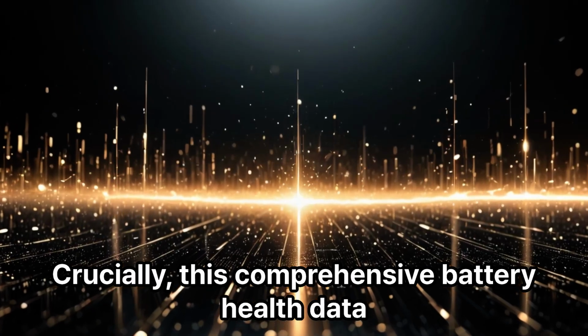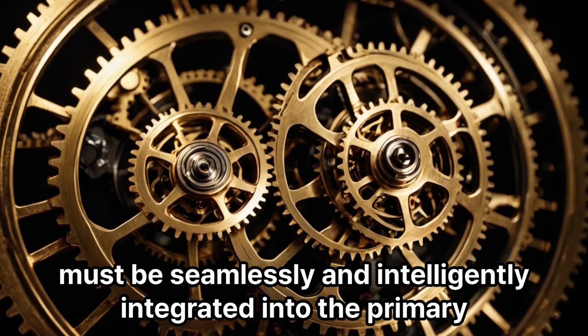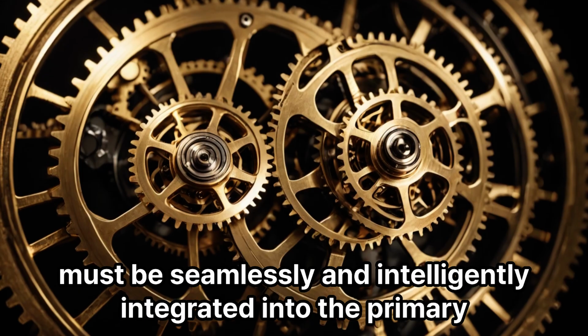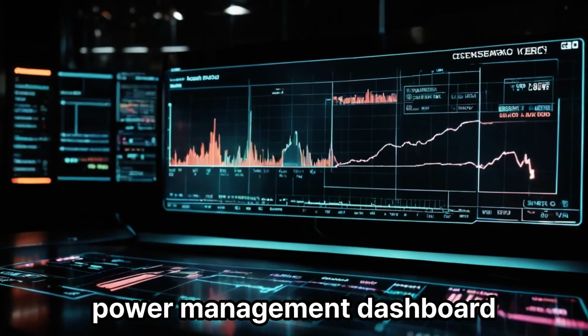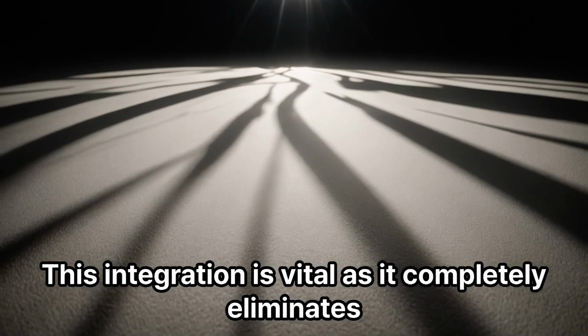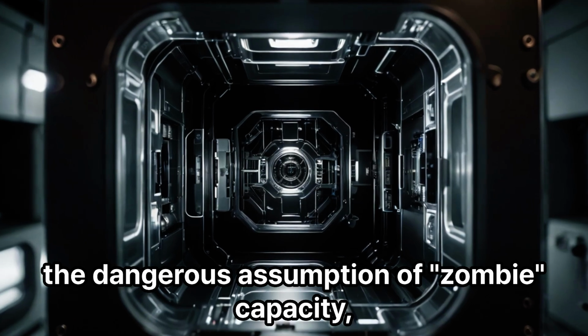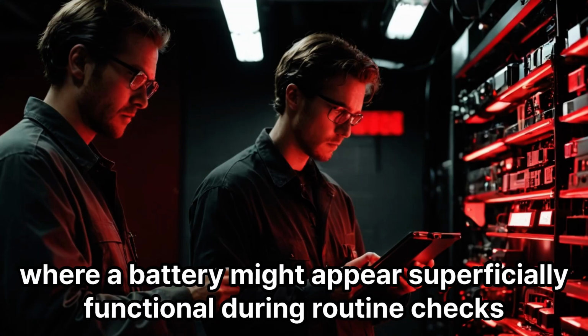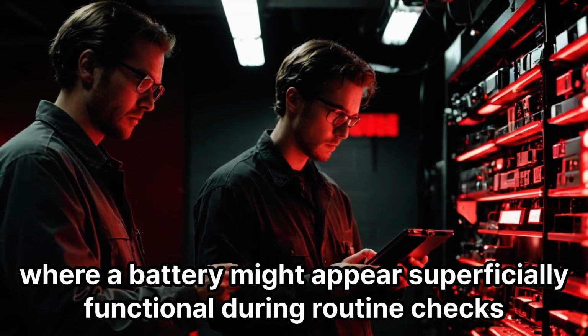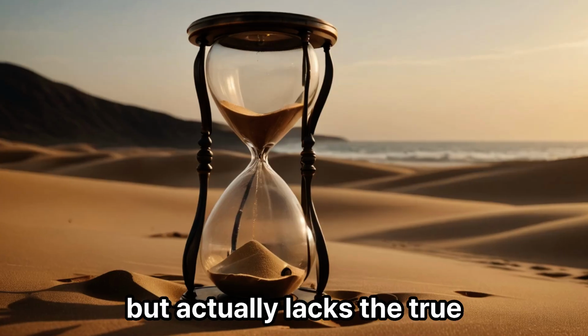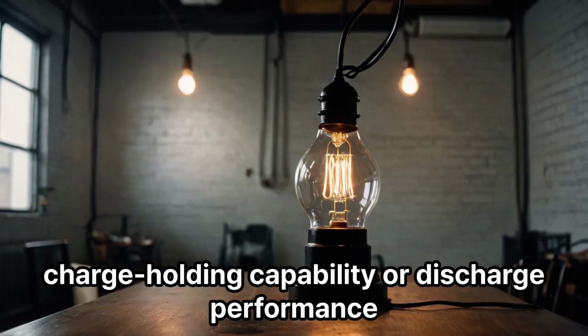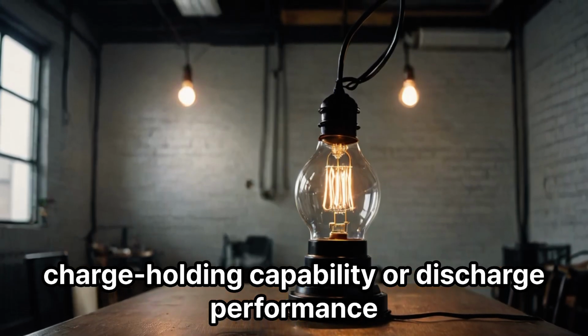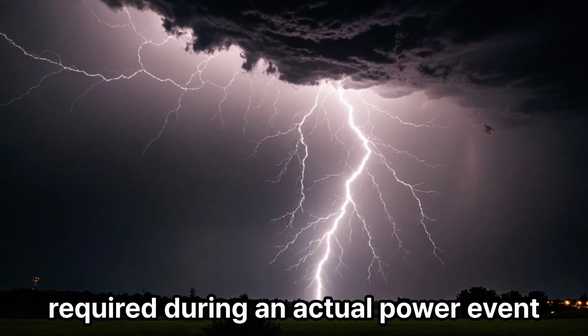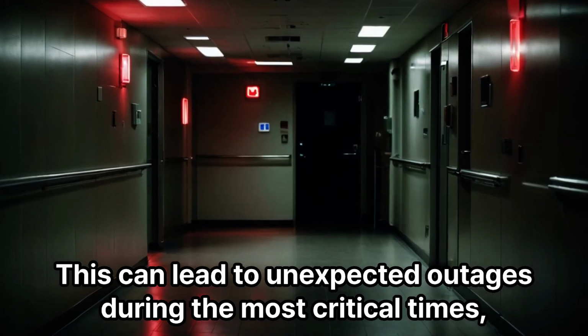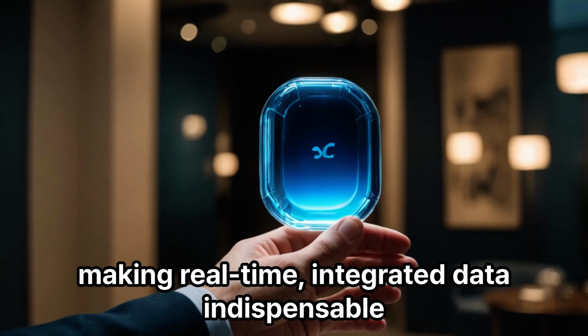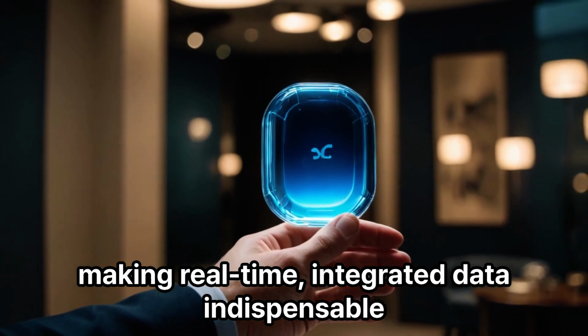Crucially, this comprehensive battery health data must be seamlessly and intelligently integrated into the primary power management dashboard. This integration is vital as it completely eliminates the dangerous assumption of zombie capacity, where a battery might appear superficially functional during routine checks, but actually lacks the true charge holding capability or discharge performance required during an actual power event. This can lead to unexpected outages during the most critical times, making real-time, integrated data indispensable.